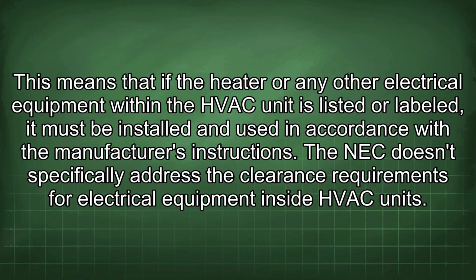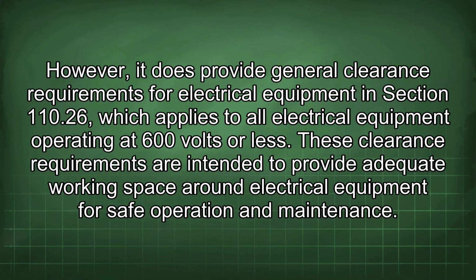The NEC doesn't specifically address the clearance requirements for electrical equipment inside HVAC units. However, it does provide general clearance requirements for electrical equipment in Section 110.26, which applies to all electrical equipment operating at 600 volts or less. These clearance requirements are intended to provide adequate working space around electrical equipment for safe operation and maintenance.